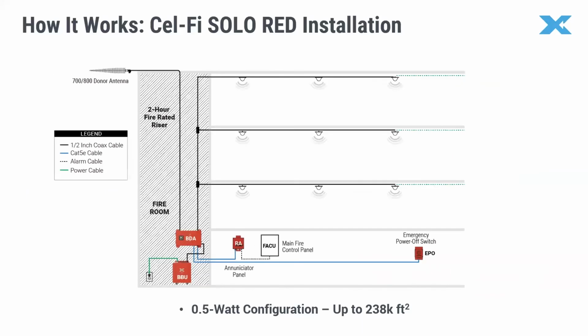Yes, right there. In this example, we're using a remote annunciator. It's the interface between the BDA and the main fire control panel. This annunciator panel is optional, since the BDA itself also has a built-in annunciator panel on the front, along with a Form C cable that can connect to the main fire alarm control panel directly.